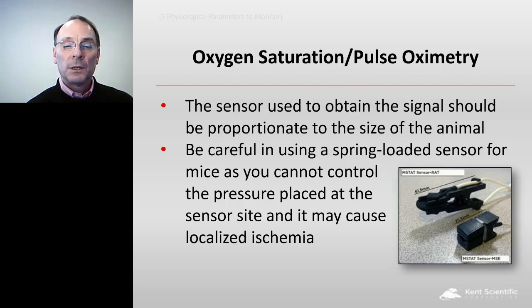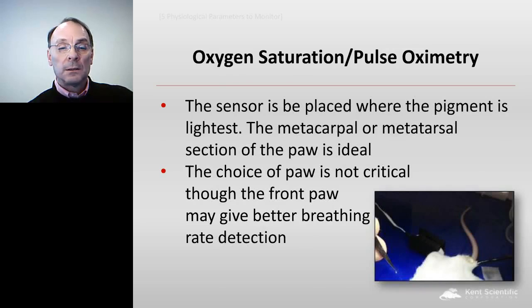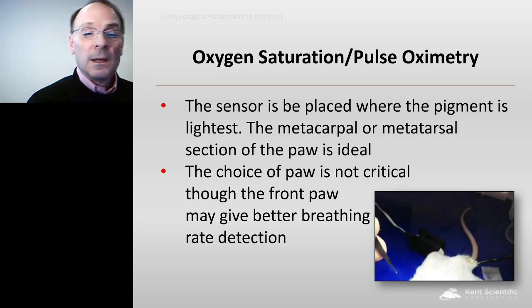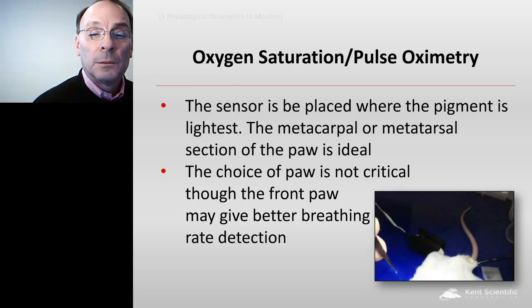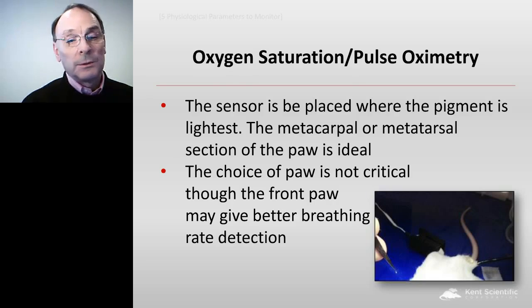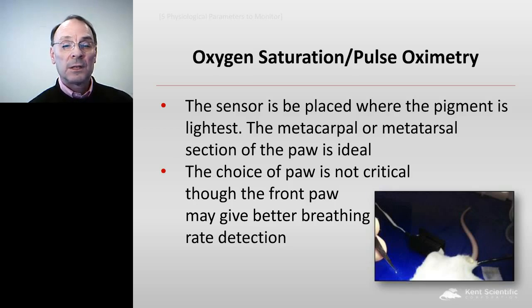There are companies that have tried using human-sized sensors on a mouse, which requires a good chunk of the animal to be used. To determine the pulse oximetry, the animal has to be shaved, and then the sensor is applied to the thigh or the neck of the animal, something typically as big as a finger. Other devices are specifically designed for the paw. With a spring-loaded clip, you have to be careful, because over time the continuous pressure will cause ischemia in the area. Since you're trying to measure the blood flow and the oxygen content of the blood flowing past the sensor, if the sensor is squeezing too tight, the blood is going to go somewhere else. And so you have ischemia and you won't be able to pick up the reading.